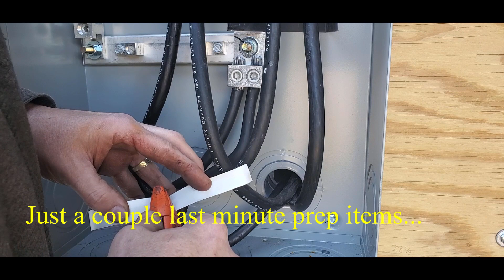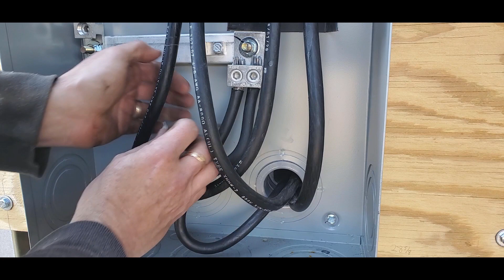Whenever you have a black jacketed cable acting as a neutral, some of the jurisdictions allow you to identify it by putting a white tape around it at either end. Sometimes they require it to be wrapped. Whatever is visible has to be wrapped with white tape. Our jurisdiction allows just the ends to be identified. So we've got our two neutrals here for incoming power on this grounding bus bar, and we're wrapping these to identify them as neutral conductors.